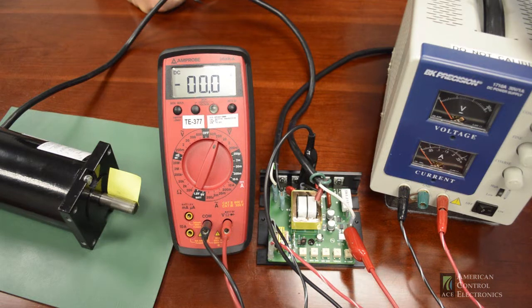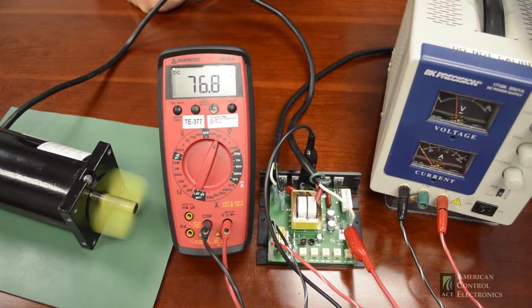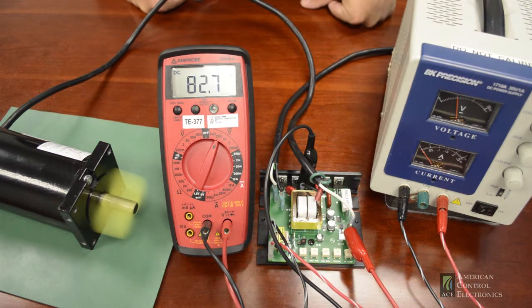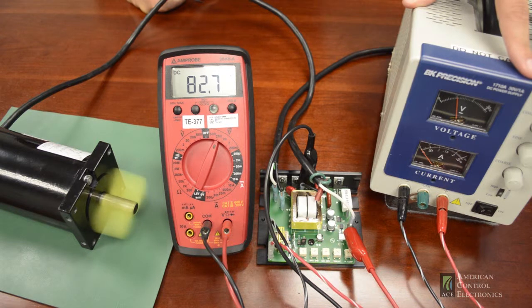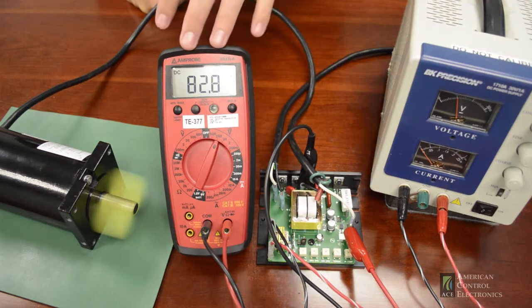We'll turn on our power supply and apply 10 volts. While we're applying our maximum voltage input signal of 10 volts, the drive is only outputting 82 volts.